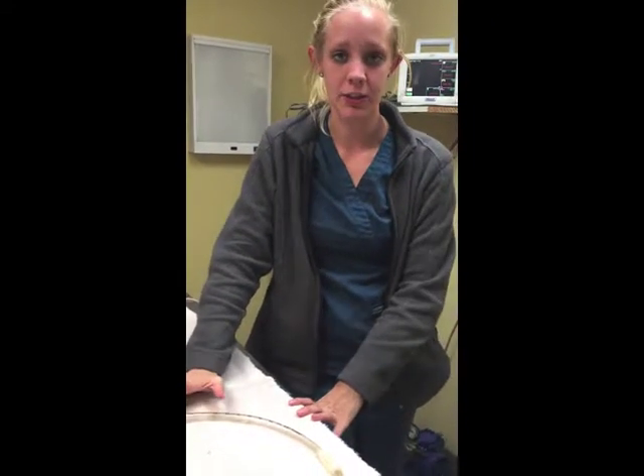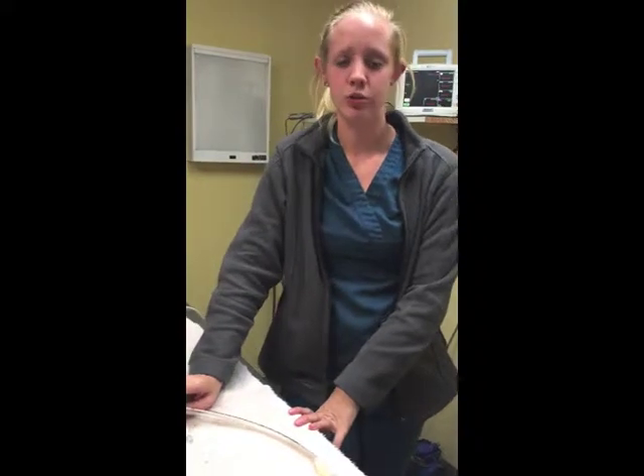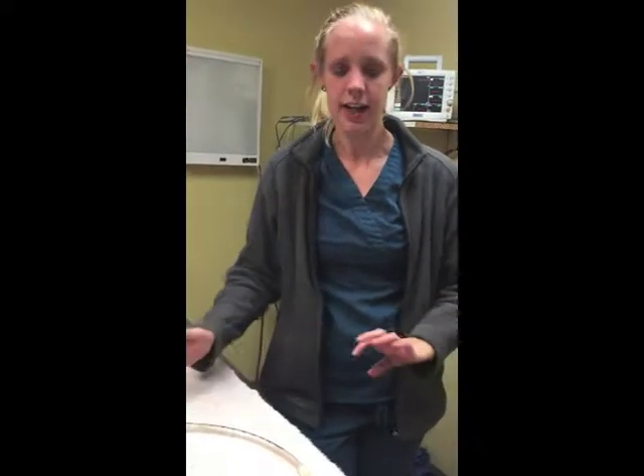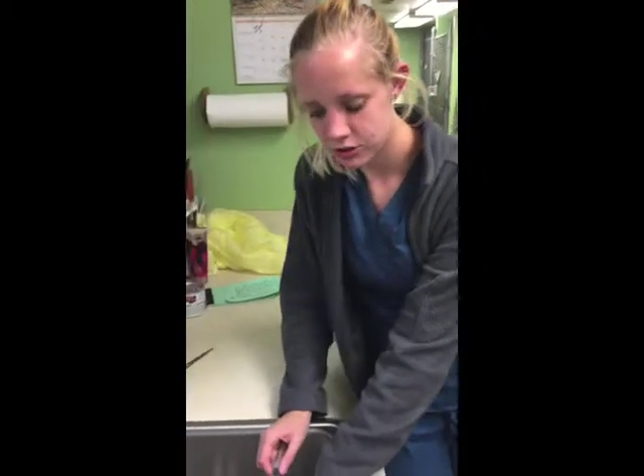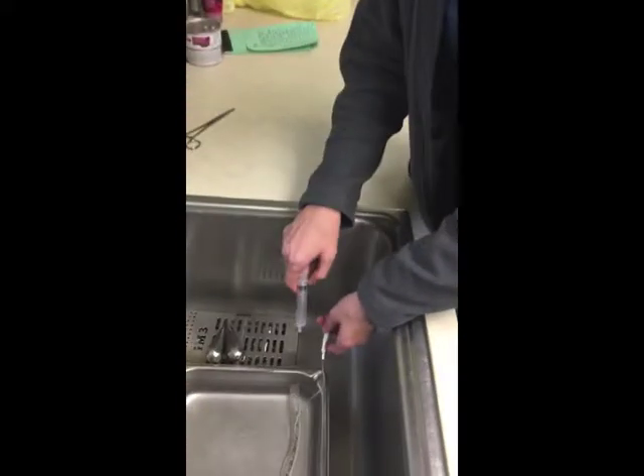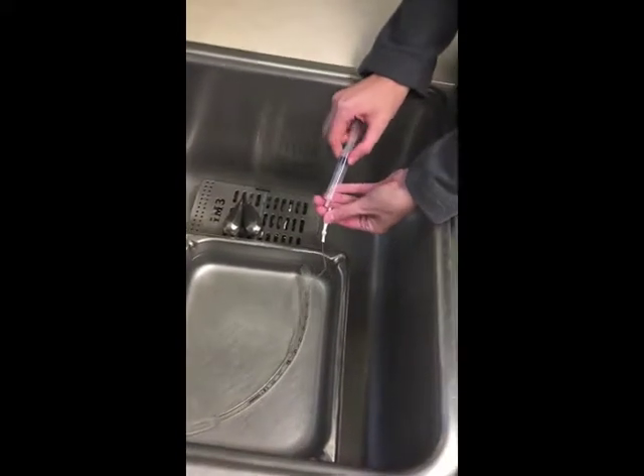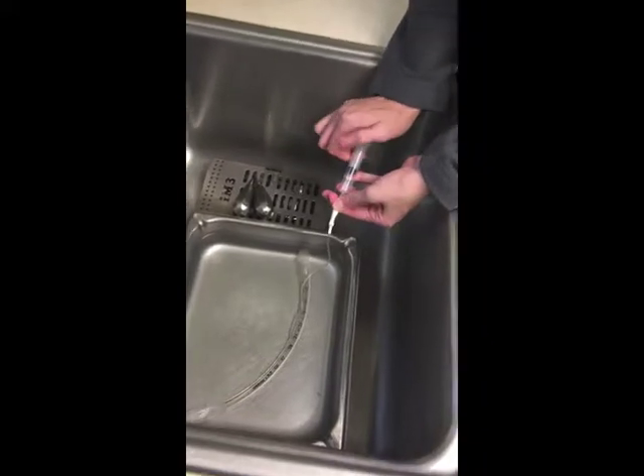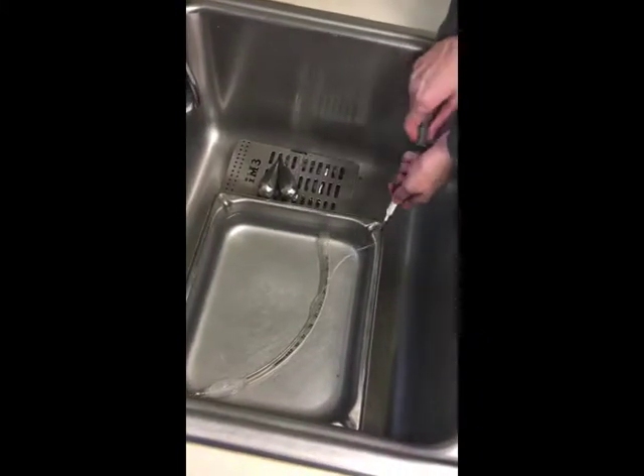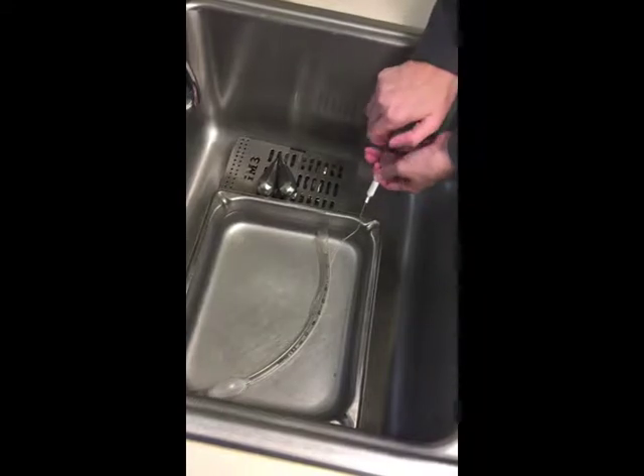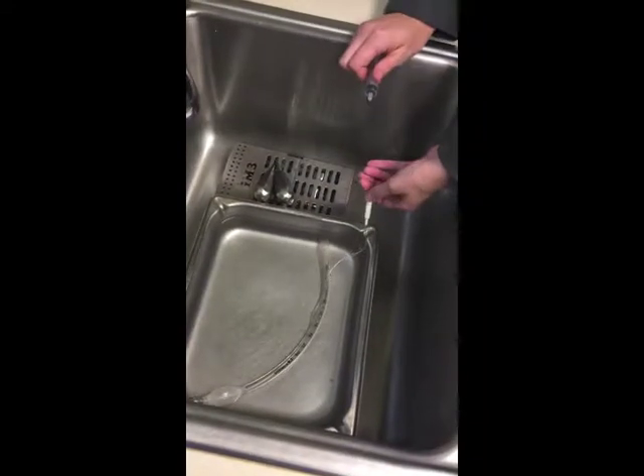When picking out a trach tube, the trach tube is normally picked out by the size or the weight of the dog, and some, through experience, have been able to palpate the trachea to know the size, and typically do a half size higher and lower as well, so you have it readily at hand when needed. When doing a trach tube leak test, you submerge the trach tube in water, and then you get a syringe and inflate the cuff, and you check for bubbles. If there's any bubbles, then you would throw the trach tube away, because it would be faulty.